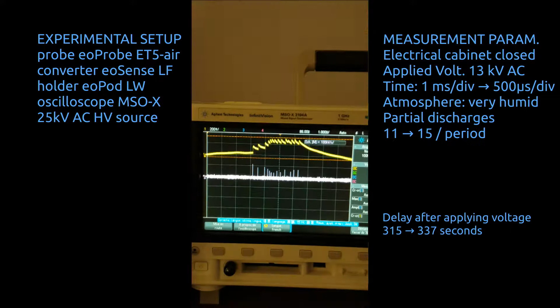As the water is still boiling, the atmosphere is getting more and more wet, and the number of partial discharges is increasing. A couple of minutes later, you can see there are 11 to 15 partial discharges per period. We are changing the time scale to have a better resolution on each partial discharge, which behavior is a perfect single exponential.